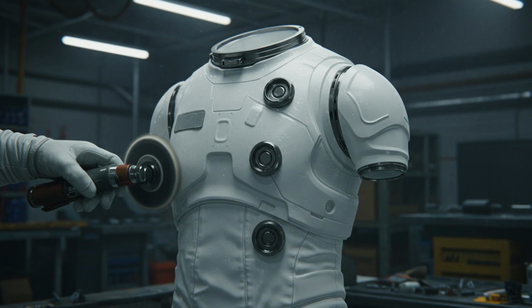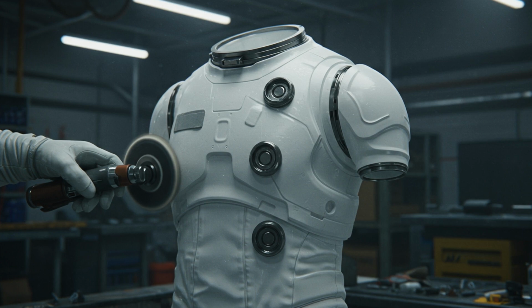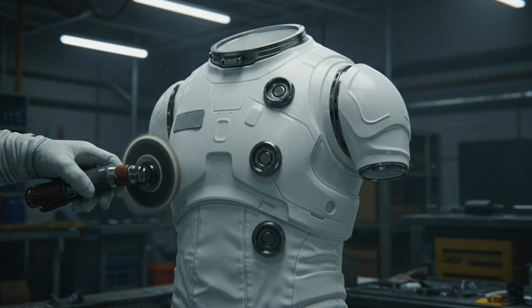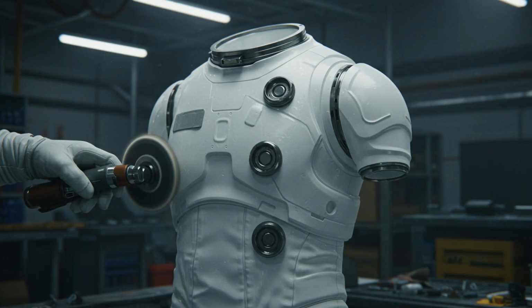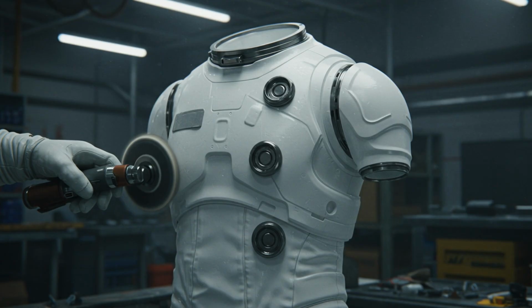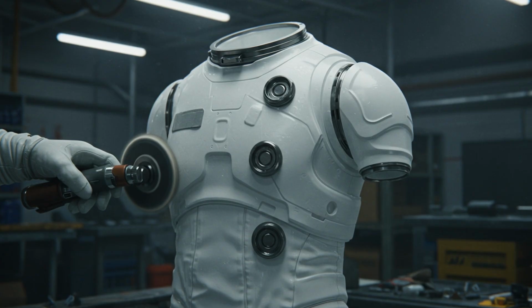For modern suits, the HUT is fabricated from high-strength fiberglass or carbon fiber composites. It is molded into a rigid, vest-like shape that provides a fixed platform for the life support backpack to mount to. The manufacturing of the HUT involves laying down thin sheets of resin-impregnated fabric into a precision-machined mold, which is then cured in an autoclave under intense heat and pressure. The result is a shell that is incredibly light, but capable of supporting hundreds of pounds of equipment without deforming.